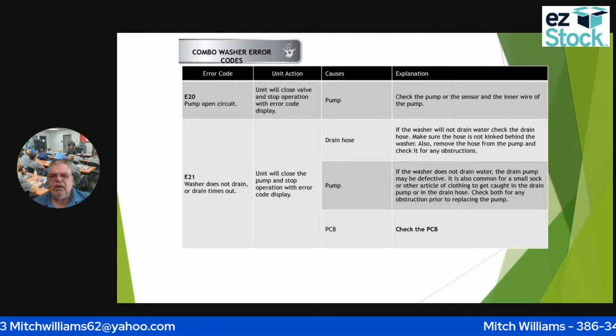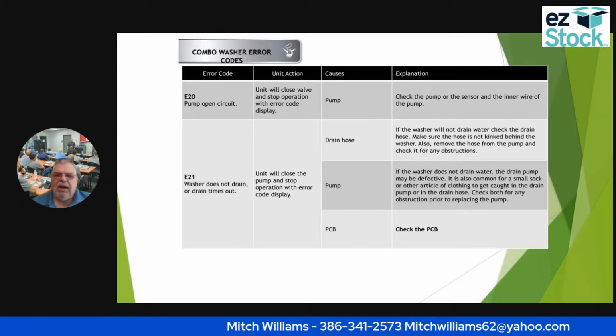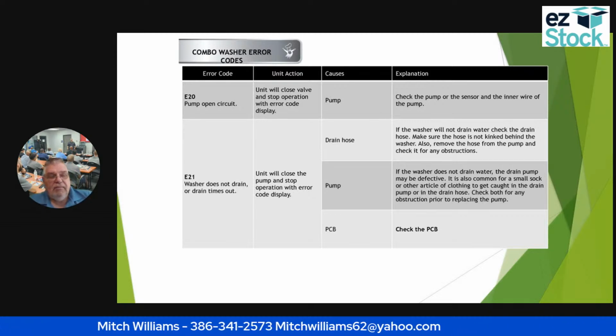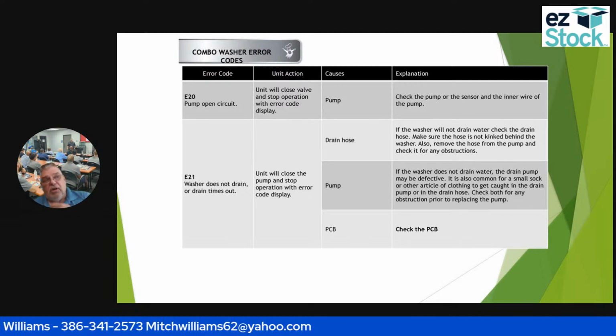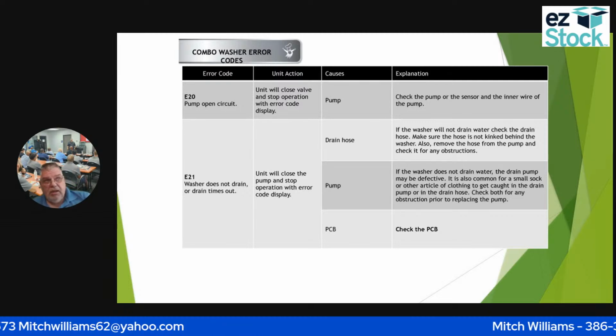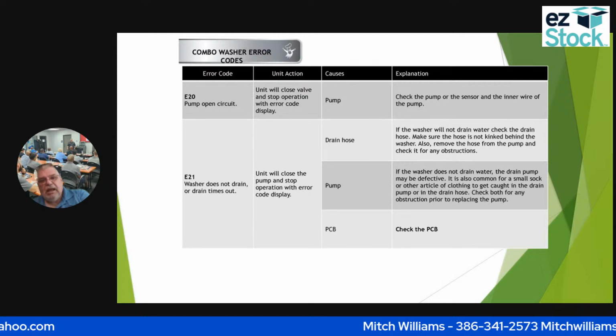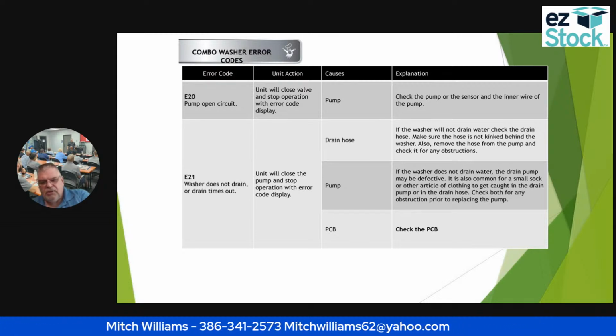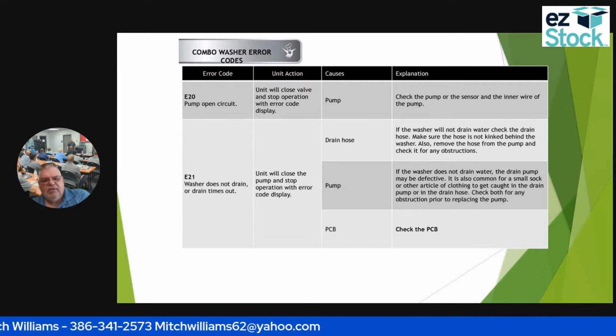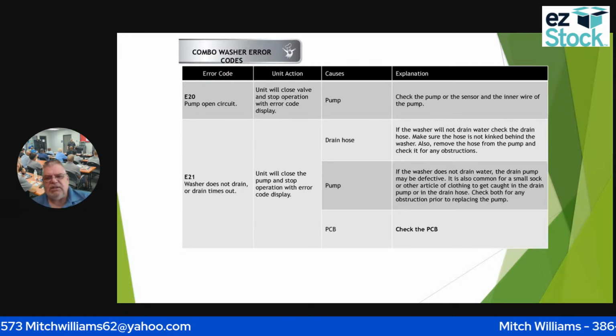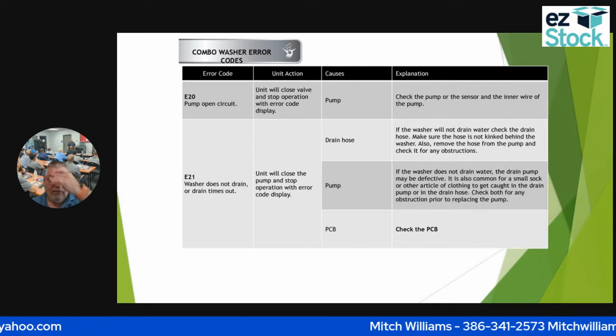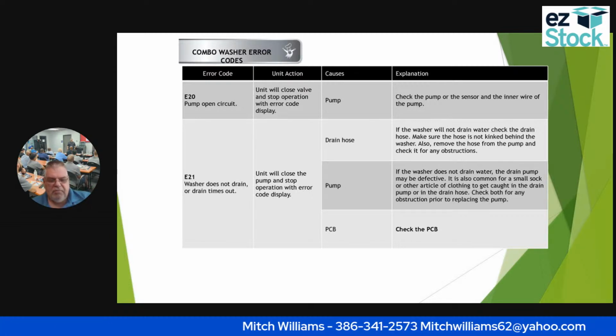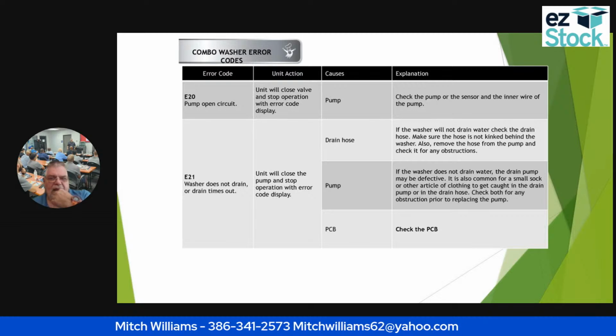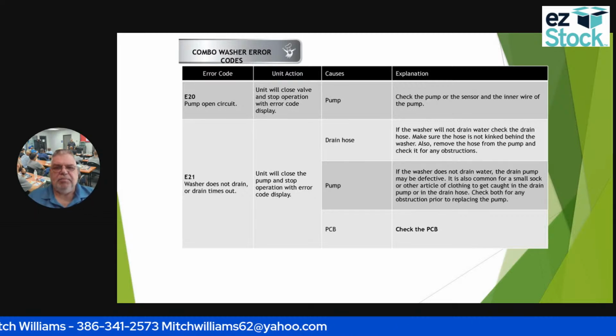out open circuit. Could be that the pump sensor is bad, and it could be the inner wire of the pump could be bad. The only way I'm gonna know that is to unplug the pump, the electricity to the pump. I can check my power to that, make sure that I have my 110 volts coming out of that. And then if that's the case, and I do not have something restricting the pump, I'm going to have to replace that pump.